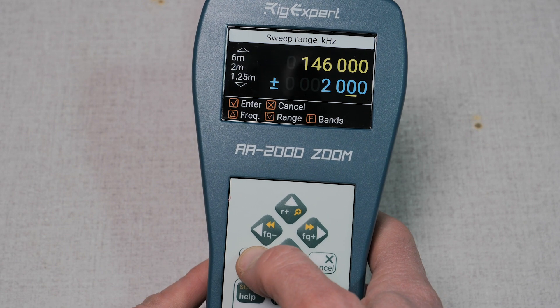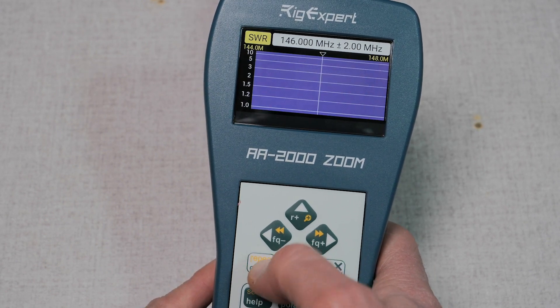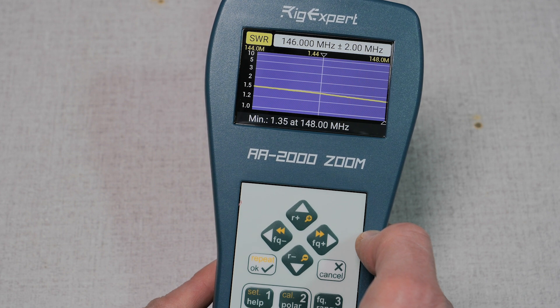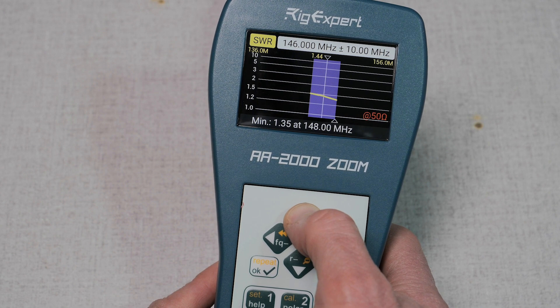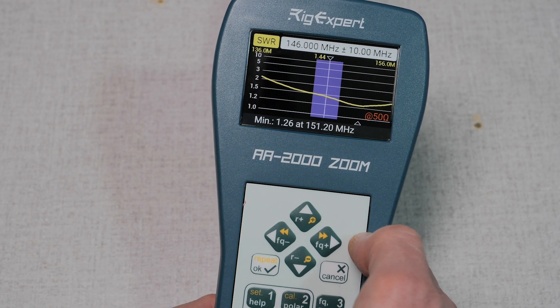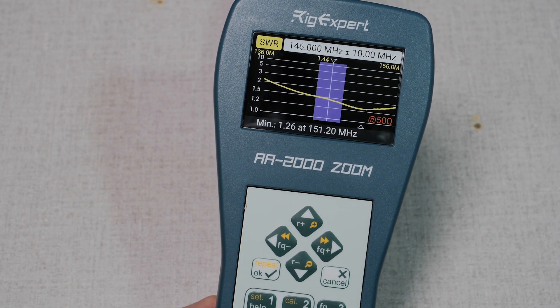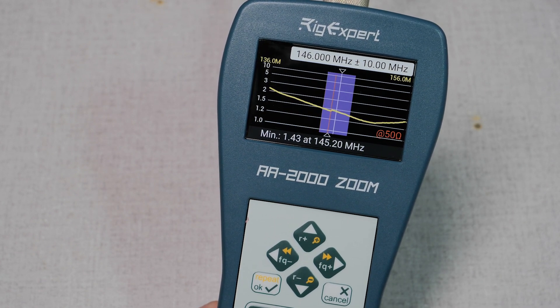Next, press four or use the menu to go to the SWR or sweep function. The meter will display the graph and you can use the arrow buttons to move the frequency back and forth and zoom in and out. This is the zoom feature of the meter — the ability to easily and quickly scroll and zoom in and out on the graphs. The meter only scans the range that is visible on the screen, so you can press the enter key again to take another scan. Pressing the cancel button takes you back to the main menu.